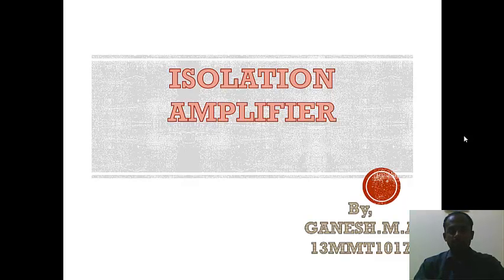Isolation amplifier is used mainly to reduce the common voltage between the amplifier side and the power source side. And to separate these two components, we are using an isolation amplifier. That's the basic function, and that is where we are using isolation amplifier.